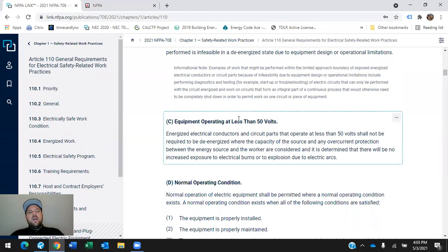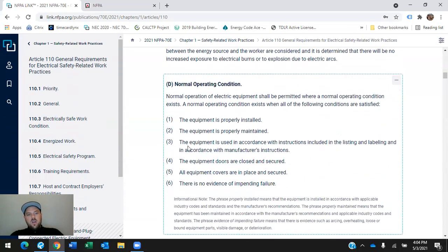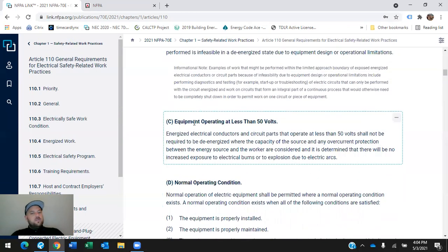C, equipment operating at less than 50 volts. Energized electrical conductors and circuit parts that operate at less than 50 volts shall not be required to be de-energized where the capacity of the source and any overcurrent protection between the energy source and the worker are considered, and it is determined that there will be no increased exposure to electrical burns or explosion due to electric arcs. So as long as we follow the parameters, we can do energized electrical work on that. But don't let that fool you.